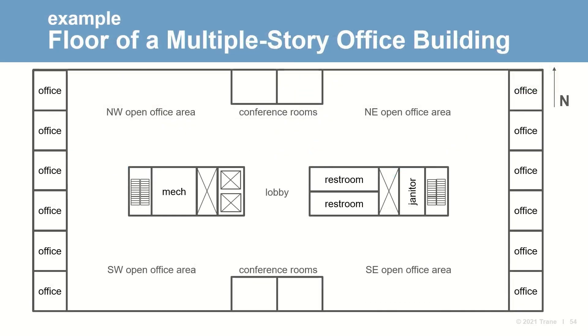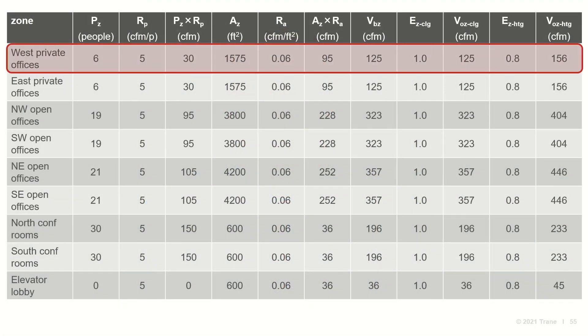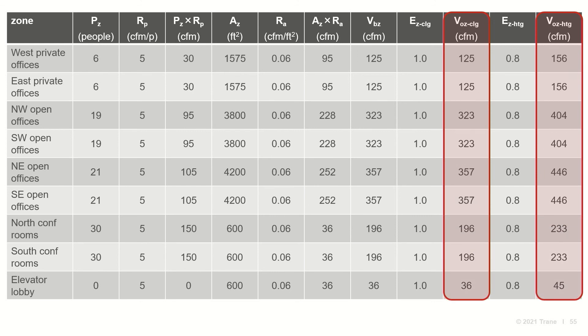To demonstrate the procedures for calculating system level intake flow, we'll use the example office floor plate introduced earlier. For each of the three configurations, the system calculations build off the exact same zone calculations. This table includes the zone outdoor air flows calculated for all zones, with the breathing zone air flows V-sub-BZ and the zone outdoor air flows V-sub-OZ, whether the system is delivering cool air or hot air for heating.